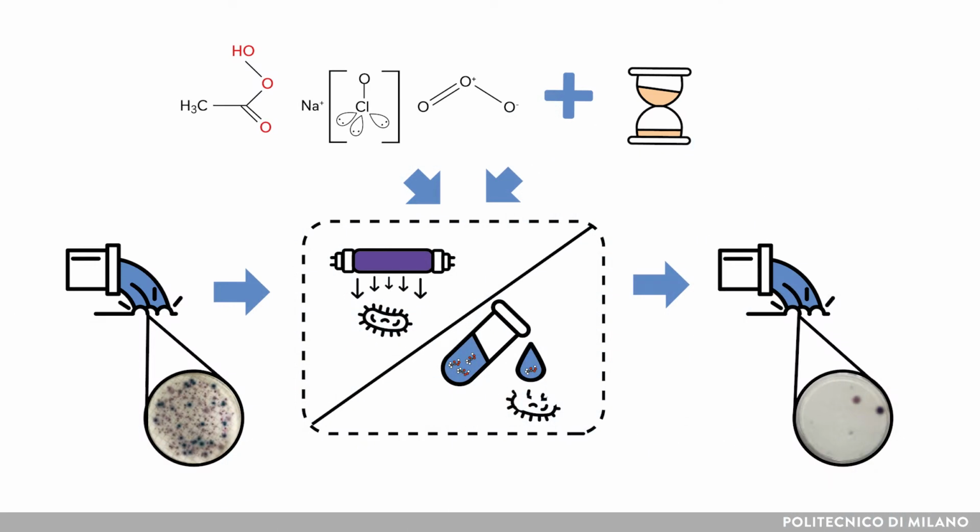Disinfectant dosage, being the dosage of the reagent or the delivered UV intensity, has to be optimized in order to guarantee the required pathogen reduction, while minimizing drawbacks, meaning residual concentration of disinfectant, which implies an ecotoxicological impact and process cost. In the wastewater treatment field, this goal is challenged by the fluctuations in quality and flow rate of wastewater to be disinfected, which impacts on two fundamental operating parameters in determining process efficiency: the concentration of disinfectant and contact time. As a result, process efficiency can be significantly affected, leading to possible unexpected under or over dosages.